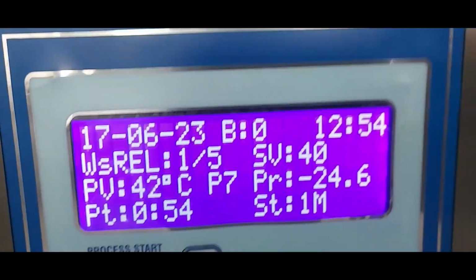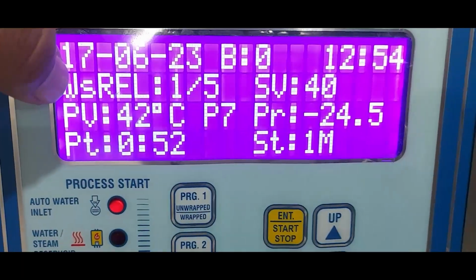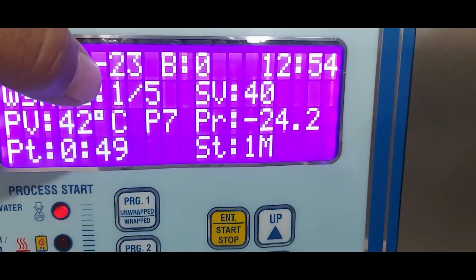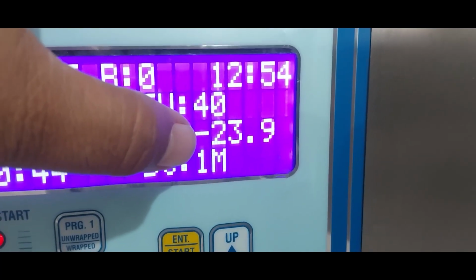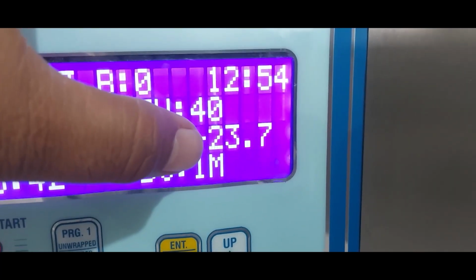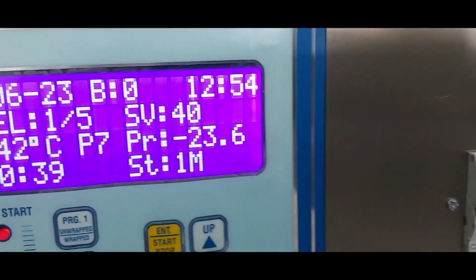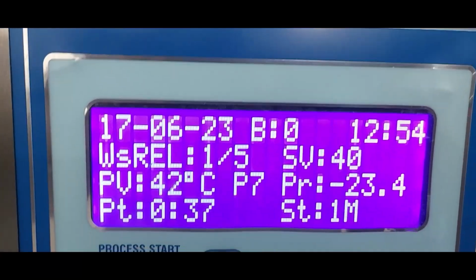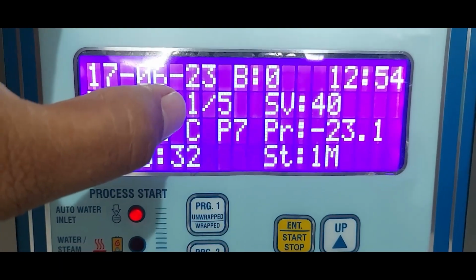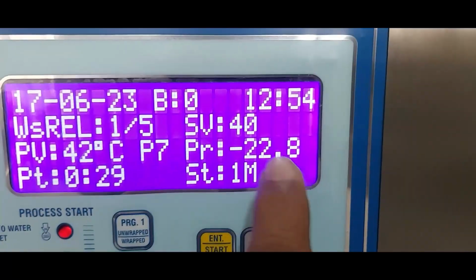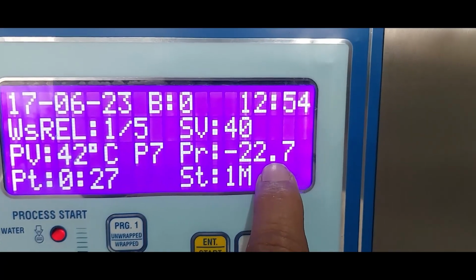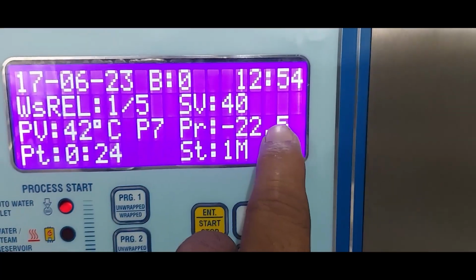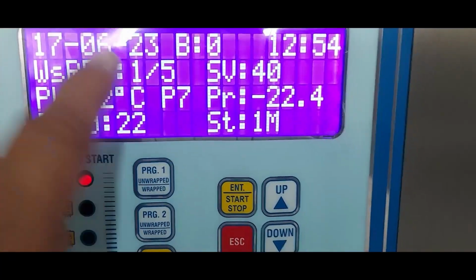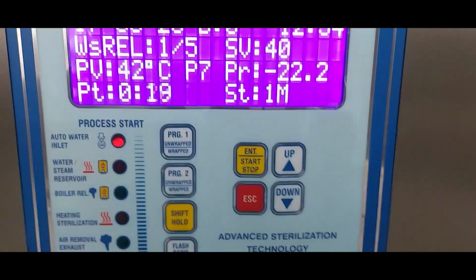Now the cycle starts for the wash cycle. Wash cycle is in release. Once the release starts, it will release the system from here, minus 25, and it will go up to minus 5. Wash cycle 1, then wash cycles 2, 3 and 5. The total wash cycle includes the 5 steps indicated here. Once it goes to minus 5 pressure, then the second cycle will start again for the wash.